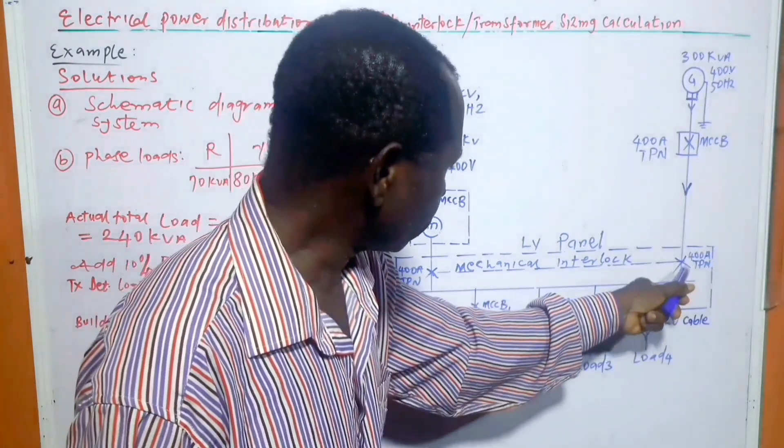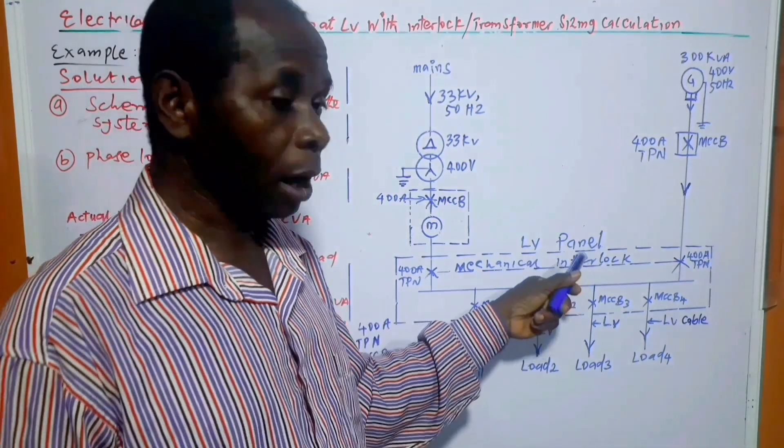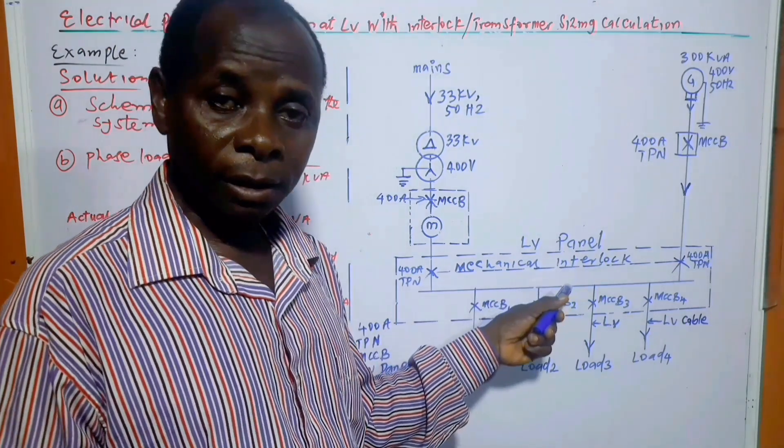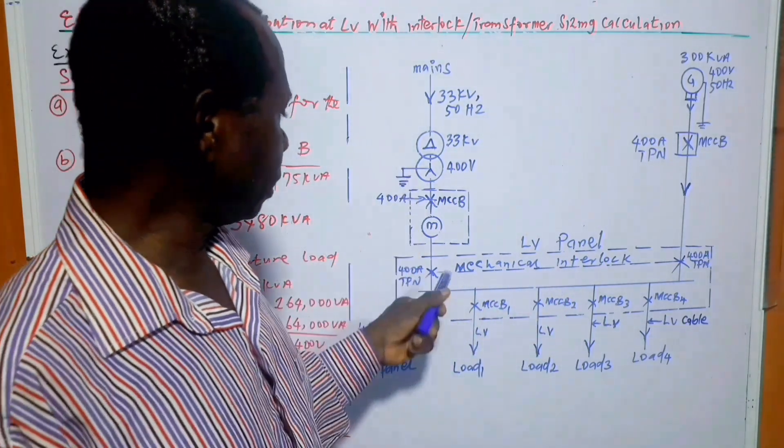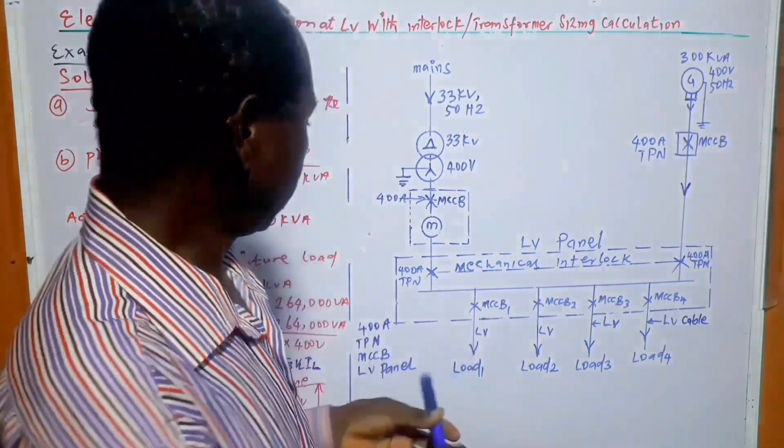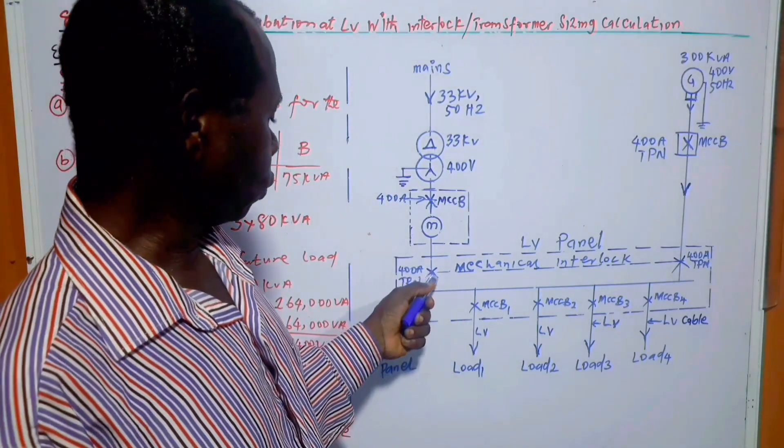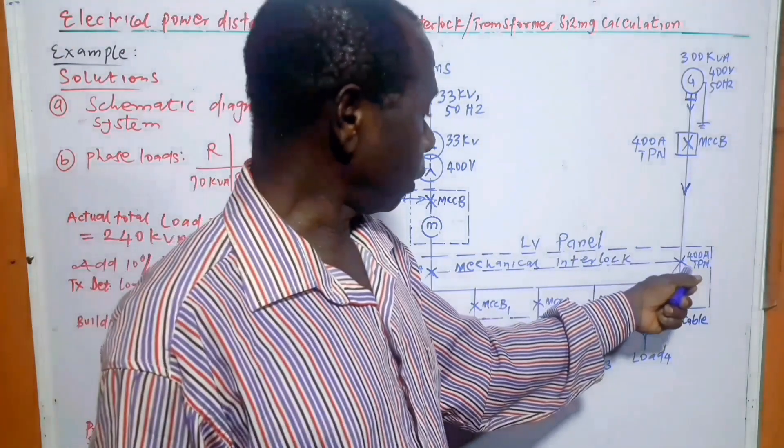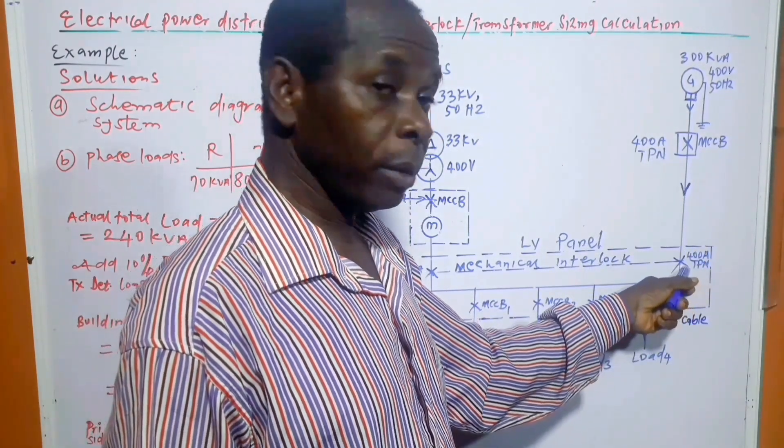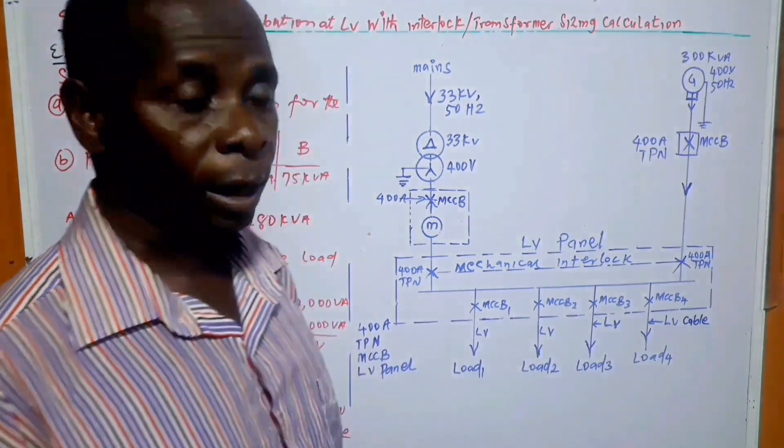So we have here, this is the interlock. This is the mechanical interlock in the sense that it is not automatic in this case. So when there is power failure, this circuit breaker will need to be opened and this one will be closed so that the generator output will come here and it will be available to the common board section and hence to the load.